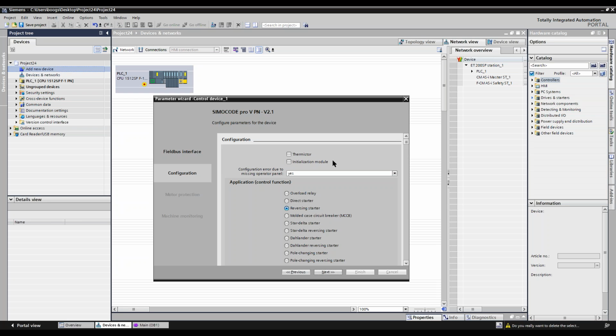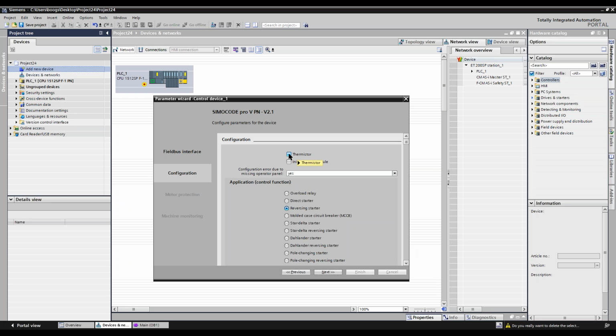You remember that initialization module that I talked about, where it's mechanically tied to the MCC bucket? If you're going to use that, you would check the box here, or if you were going to use the thermistor inside capabilities of the SIMOCODE, you would check the box here. For our purposes, no. And then you remember my buddy, I said he had that MCC bucket project where he had 35 buckets, and he wanted to use one of the operator panels instead of buying 35 of them, one per bucket. So what we did here is we clicked no. We said configuration error due to missing operator panel. Just say no, because then when he unplugged that little operator panel and put it away, and all the Simicodes didn't have it plugged in, it didn't fault. But for my purpose, I have an operator panel. If I unplug it, I want it to fault.